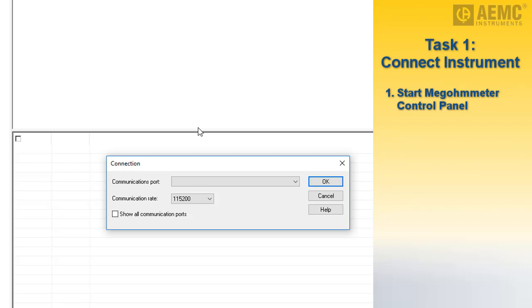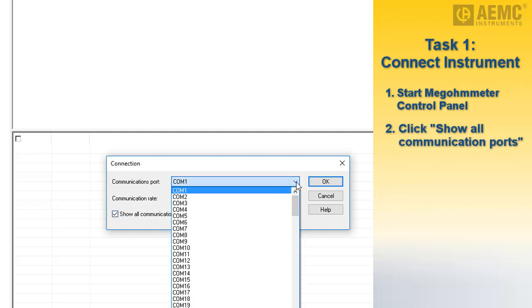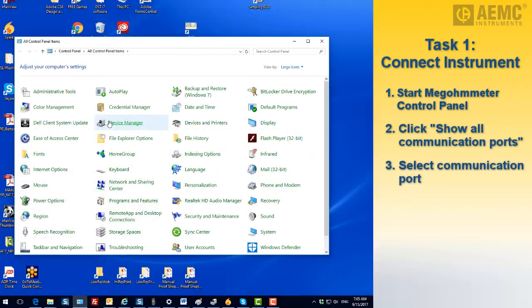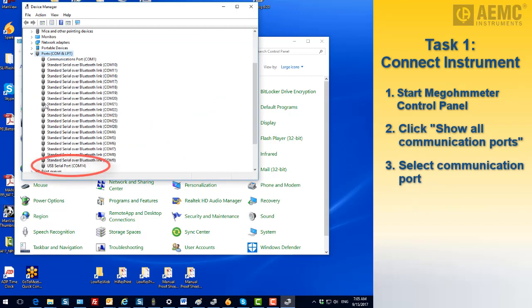Click the checkbox Show all communication ports. Then click the drop-down list in the Communications Port field and select the port through which the instrument is connected. If you don't know the port number, open your computer's device manager and click the Ports folder. The port number for the connection to the instrument will be listed. If you can't tell which listed port is the instrument, unplug it and plug it back in. The port will disappear while the instrument is unplugged and reappear when reconnected.